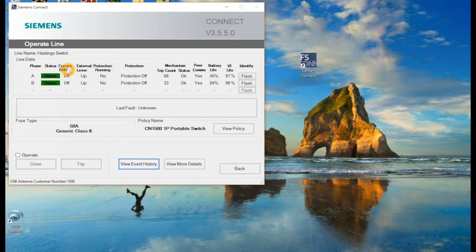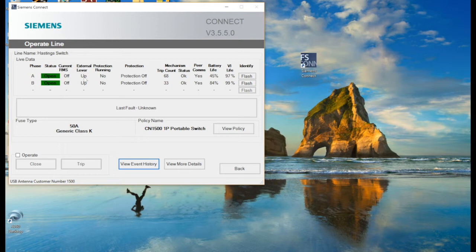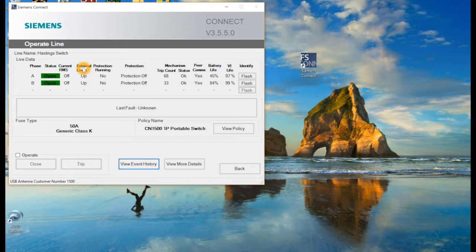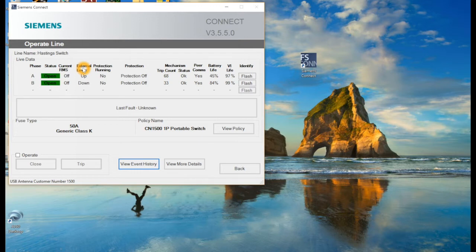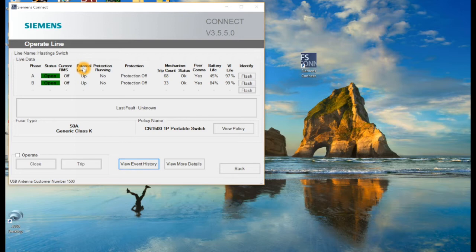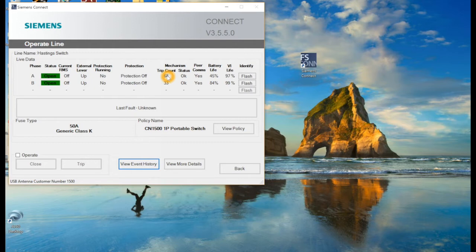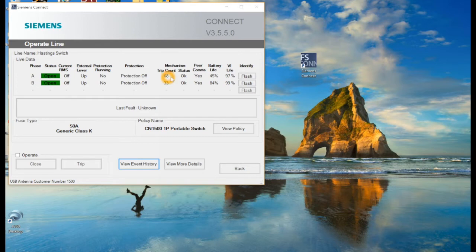Now this menu is where you're going to get all of your information, all of your most useful information. So here I've designated which unit is on A phase, which unit is on B phase, and as you can see both units are open. So the current RMS values, of course I don't have this right now on an energized source, so it'll be turned off. That function you can turn on and you can receive information from there. Here in the external lever, what that is, that's your safety release latch. So when you wanted to cancel that function, I'll just show you here. We'll go ahead and pull that open on one of the units, and now you can see one is up, one is down, just letting you know whether that lever is up, down or ready to operate. So we'll go ahead and close that back up. So now the lever's in the up position. The trip count here, you can see that's how many times it's been operated. Each unit here has been a little different; we've been playing around with them here in the shop.